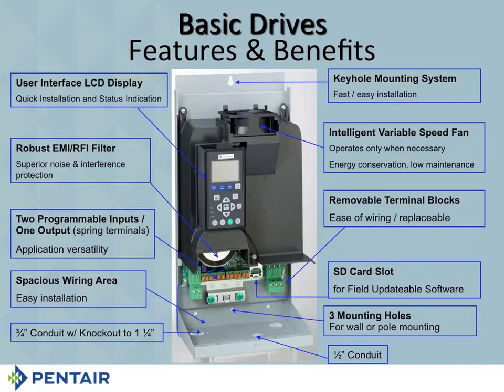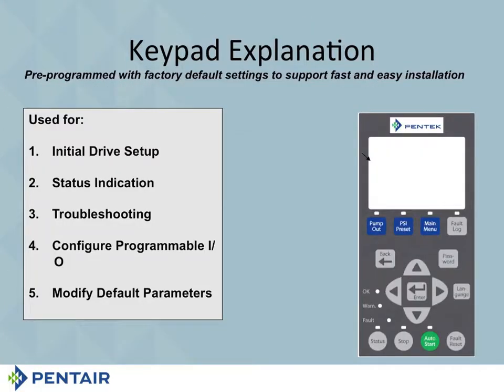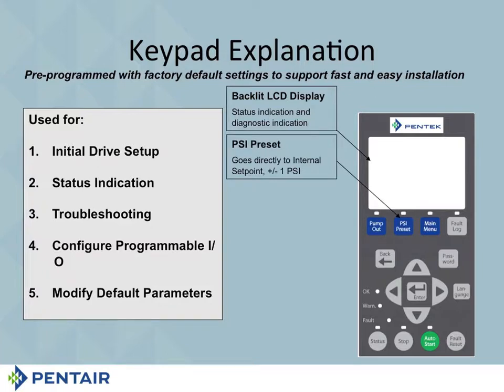And then we're going to talk about this keypad here. When you look at the keypad, yes, it does have a backlit LCD display on there, so it's very easy to tell what's going on. There are 3 blue buttons, and the one in the middle there says PSI preset. That is directly connected to the internal set point, and the internal set point is the point at which you always want the drive to run at. One of the ways that you can change that internal set point, and there are several, is right here by pushing that PSI preset button.